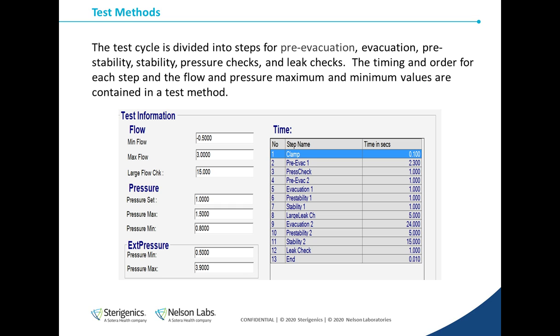Test methods control how the test works. All methods follow the same series of steps. The timing for each step can be changed in the individual methods, as well as the limit values. The picture here in the slide shows an example of a vial method. This vial method takes about a minute to complete. Different sample types and sizes may require adding or subtracting from each time spent in each step to create a suitable test method. For an inline manufacturing mass extraction test setup, where the fixtures are built specifically for a single sample type, the method can be optimized to run in just a few seconds. We've opted for slightly longer test methods so that the method can be used for a wider variety of test samples.